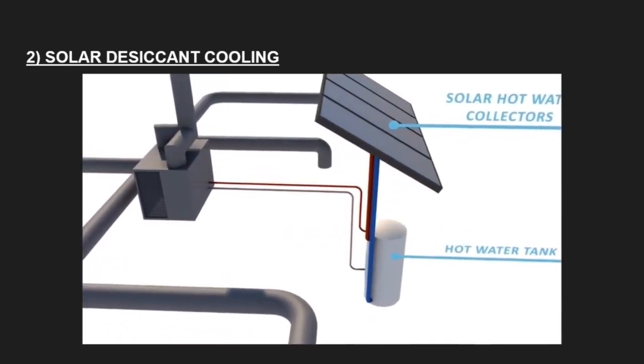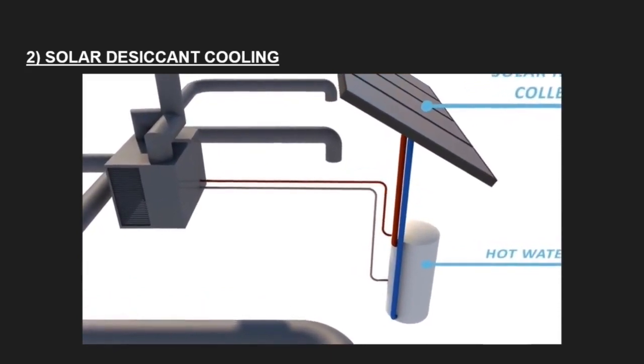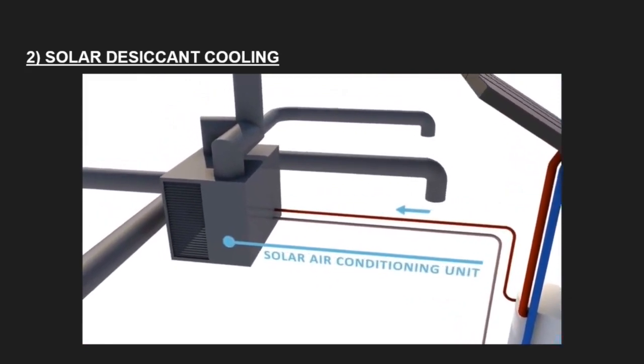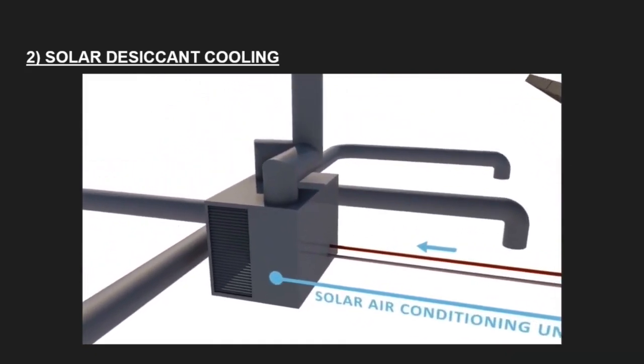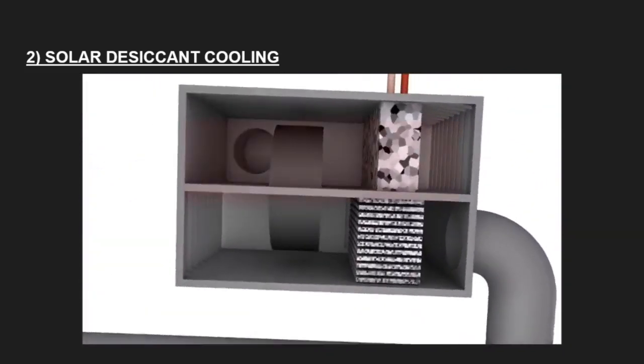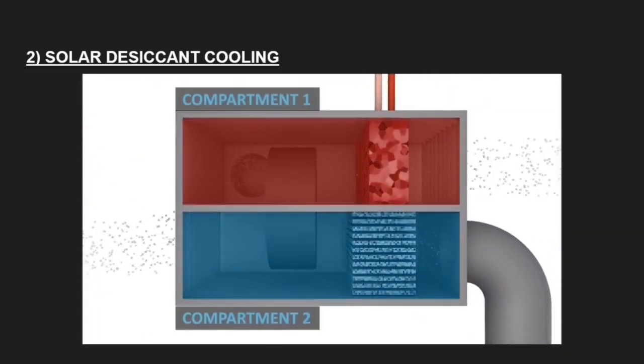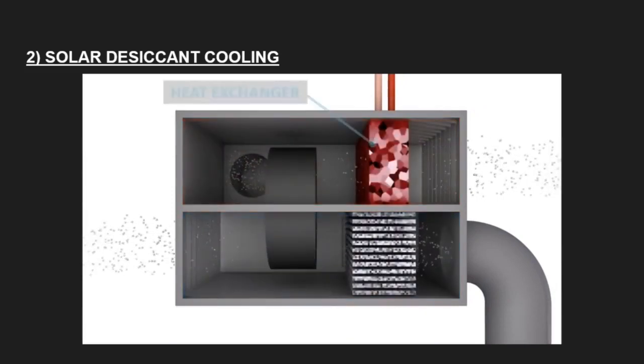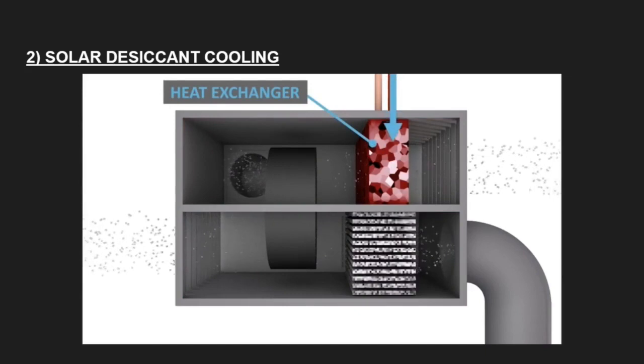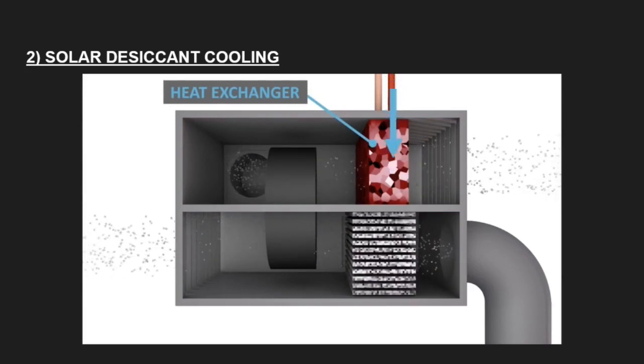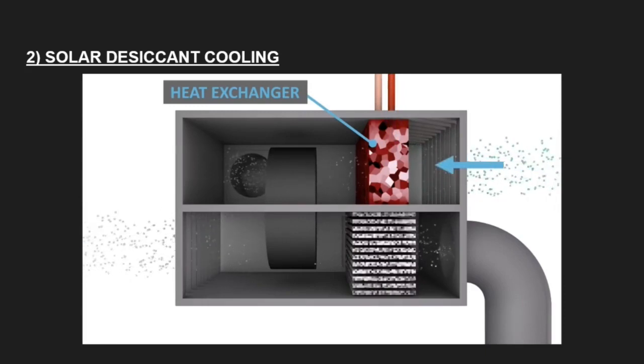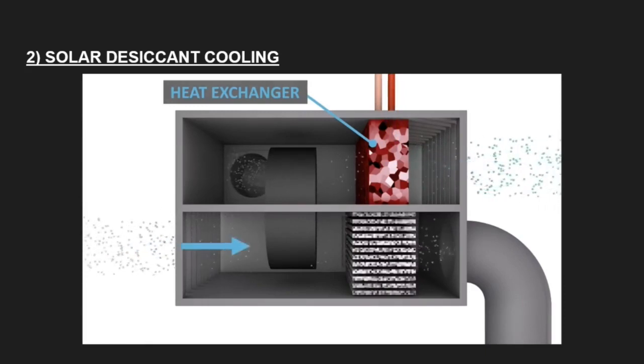CSIRO's solar air conditioning is an innovative three-in-one technology that provides hot water, cooling, and heating using only a fraction of the electricity of current systems and halving greenhouse gas emissions. The process begins with a typical solar hot water system. Water is heated by solar panels and stored in the hot water tank. A portion of the hot water is diverted into the solar air conditioning unit which is divided into two compartments. The hot water enters a heat exchanger in the first compartment.